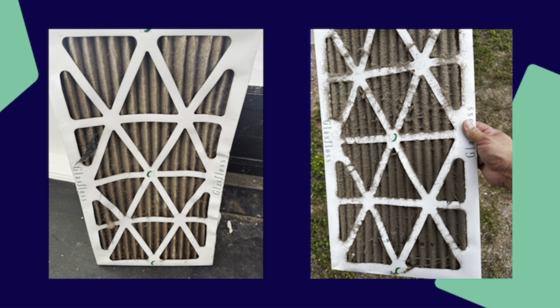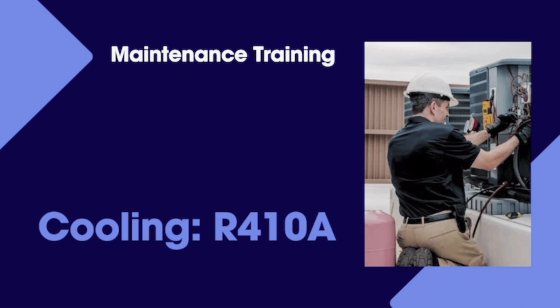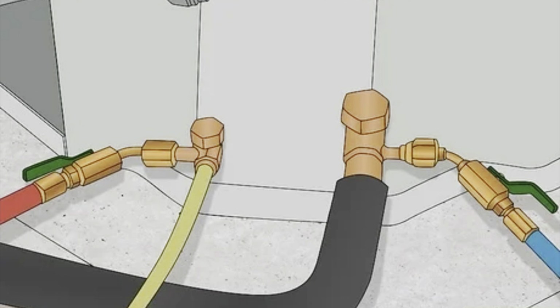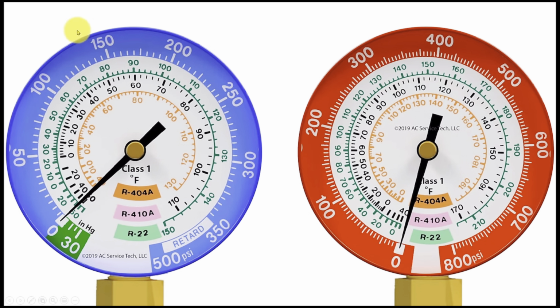A dirty filter can heavily impact your refrigerant pressures and overall the ability to cool, which is the next section, cooling. Gauges are to be installed like this. The blue line goes on the thicker low side, and the red line goes on the smaller copper line, which is the liquid line or the high side. In order to read gauges, we must get acquainted with them.